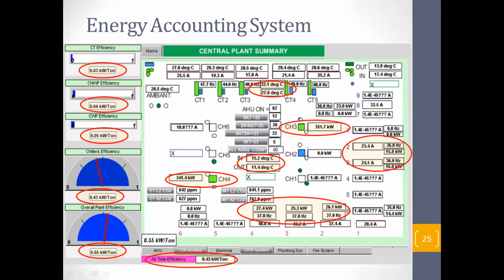You know that with a VFD, power is proportional to the cube of speed. So when you run them at lower speeds, right, you save more energy. So even after running all 5 cooling towers and 3 condenser water pumps, they have still achieved the required benchmarks. This is something for you to think about, because we cannot discuss all the details since it's building specific. But the reason I highlighted this is for you to rethink: if we run 2 chillers, should we run only 2 cooling towers? Can we run more? Only 2 condenser water pumps, or can we run more? That you need to study.